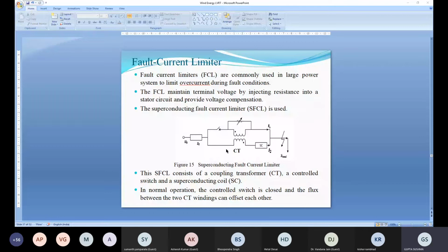Under normal operation, this switch is closed and the flux between the two CTs offsets each other. So the resistance offered by this fault current limiter will be low. But at the time of overcurrent, during the transient period, this control switch will open, and this circuit is disconnected. Only this winding and the superconducting coil remain in the circuit.